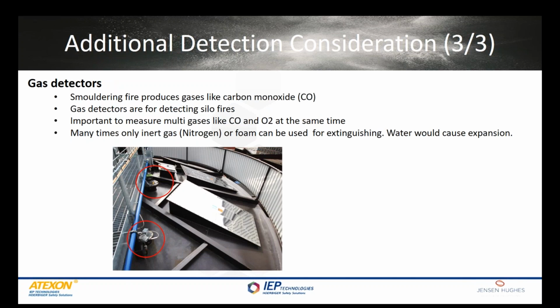And the last additional detection consideration is gas detectors. They are used to monitor fuel storages like silos to detect smoldering fires. This is only monitoring because, due to the high silo volume, it's not possible to use a conventional water extinguishing system to suppress silo fires. Water may also cause excessive expansion of biomass, and therefore water is not typically used.